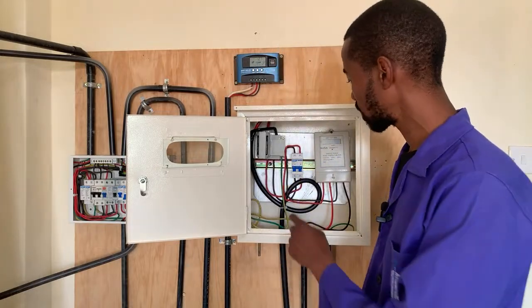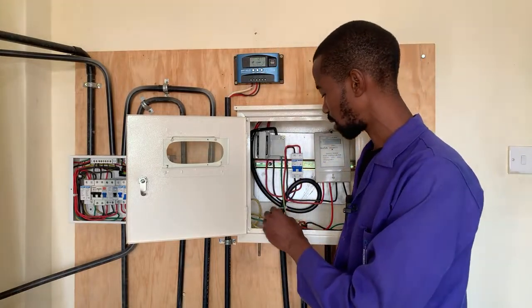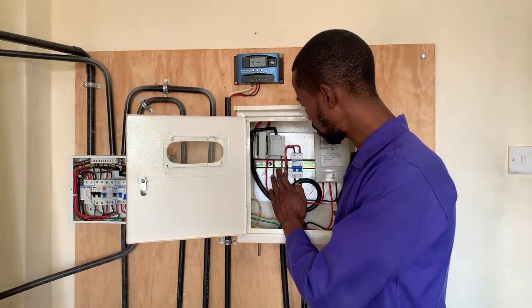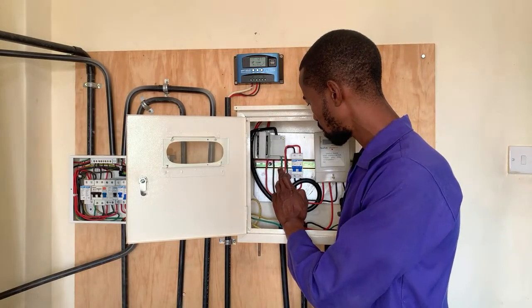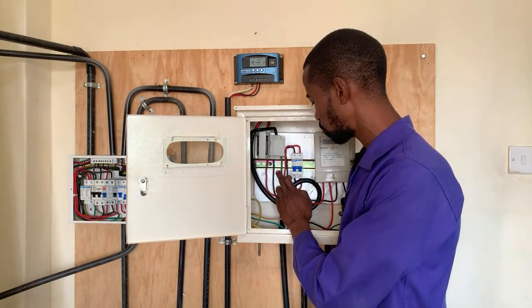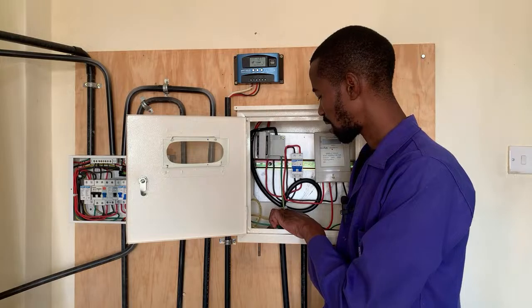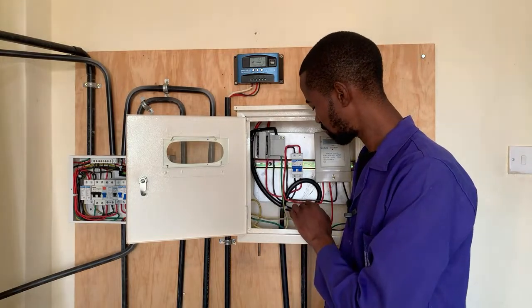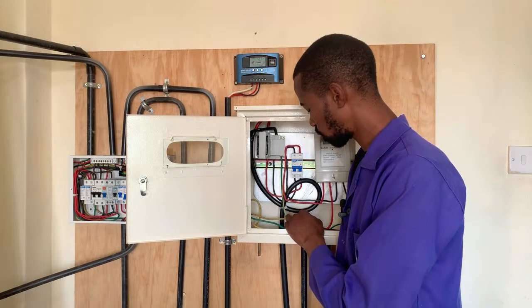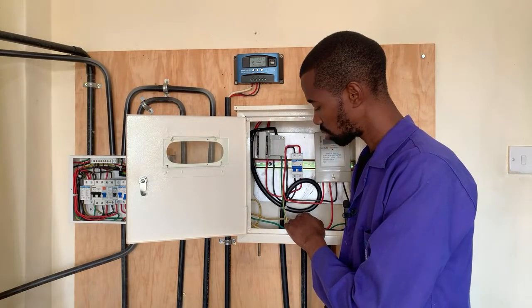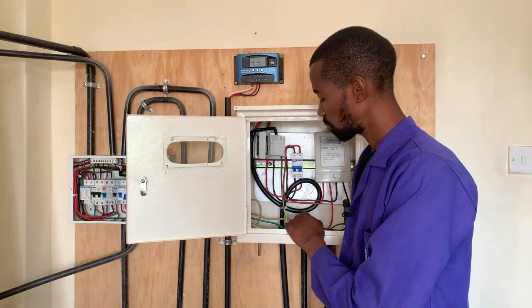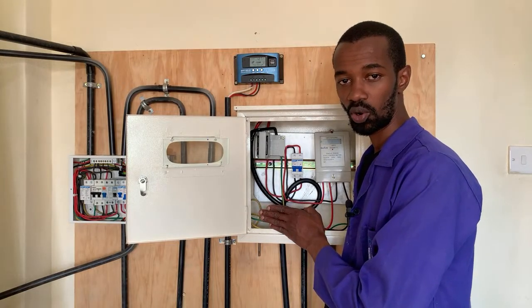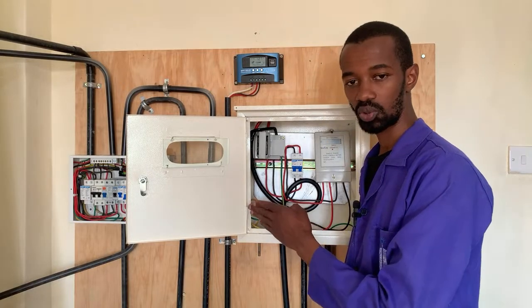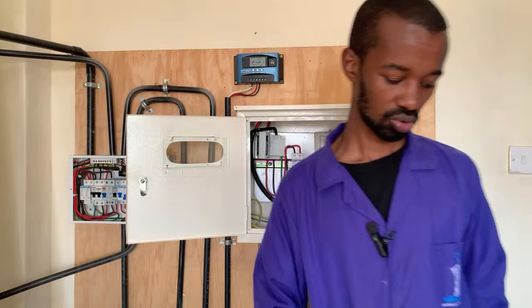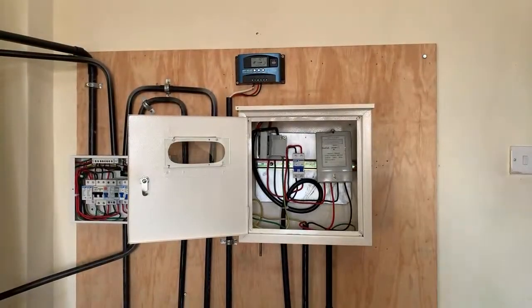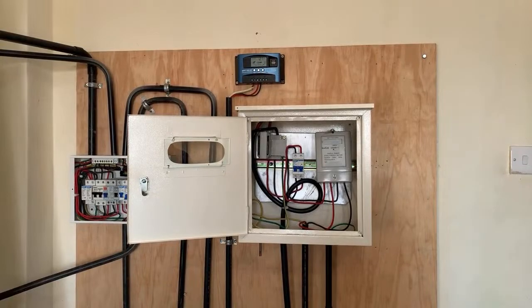Number one, loose connection of the earth cable. Now, for us here, we normally bond the neutral and earth connection at this part. We also have the connection at the meter box where the earth connection goes all the way to the ground, connecting to our earth rod, and another connection going all the way to the house or consumer unit. Let me take my camera closer so I can give you a clearer picture of what I'm talking about.